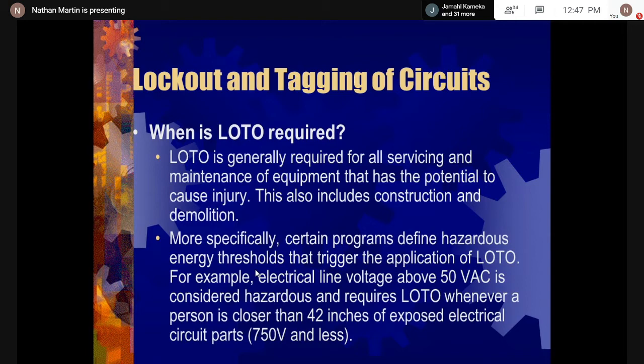All right, when is LOTO required? I would say LOTO is generally required for all servicing. I need to tell you this because you can't service a machine when the machine is running, right? Most of the time, you have to perform mechanical servicing on the machine as well as electrical servicing. And if it's a rotating machine, even if it's not a rotating machine, you need to lock out and do your tag out processes, put your tag that the machine is being repaired and maintained, so that nobody can go and energize it. Now, this is a very serious situation.